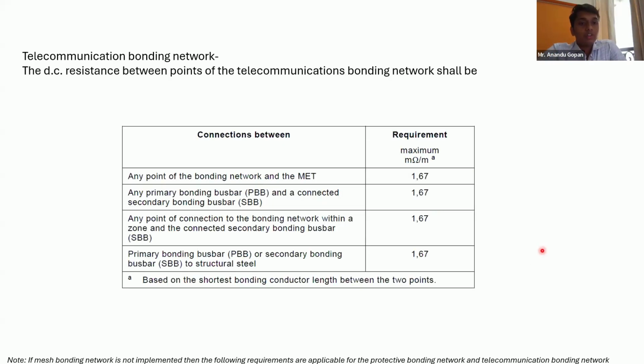When using a telecommunication bonding network without a mesh bonding system, just a plain telecommunication bonding network, you have things called PBB, the primary bonding bus bar, and the secondary bonding bus bar, with interconnections between all of these points. In your server room, you'll have your racks, cabinets, and all of those things.